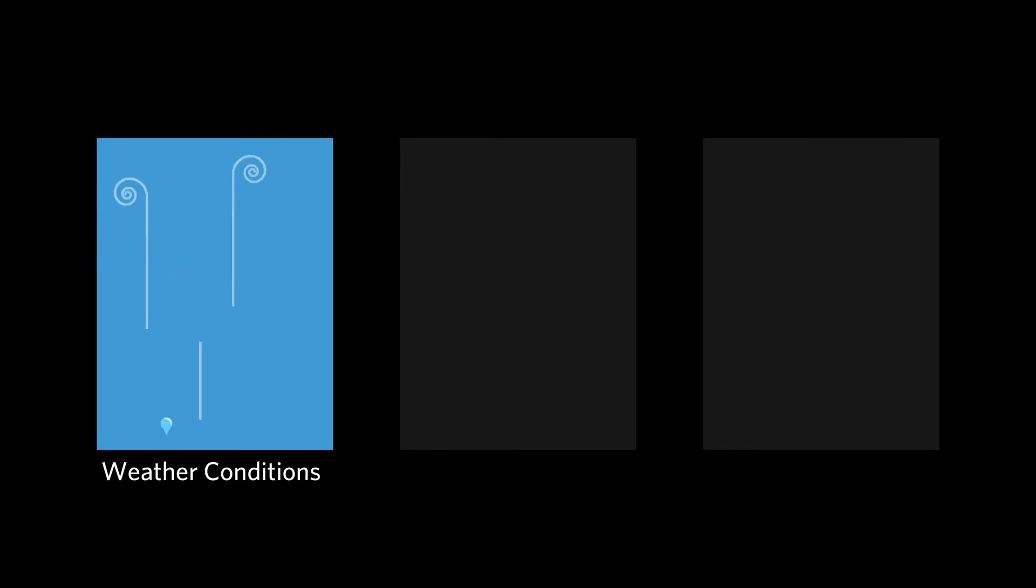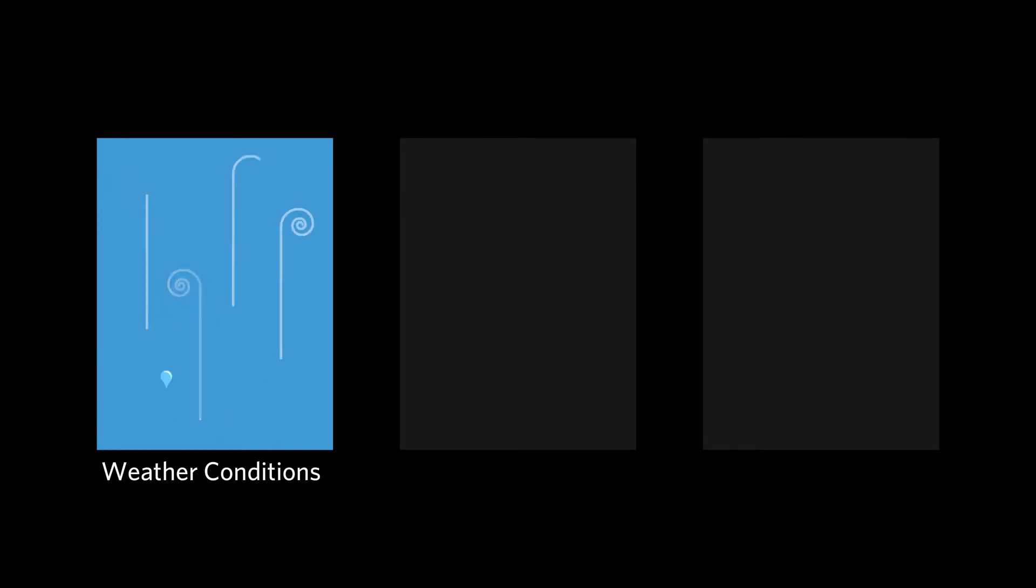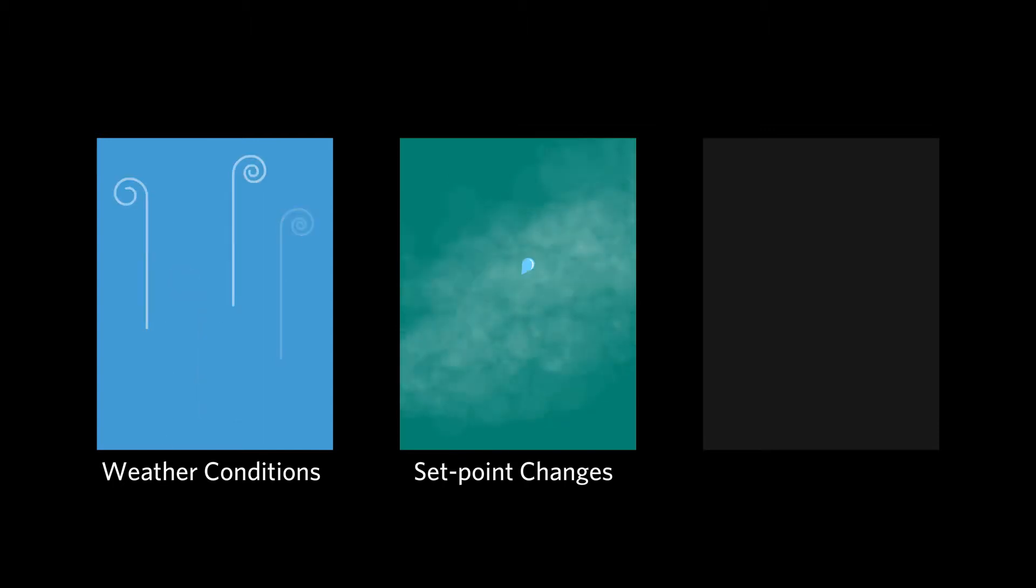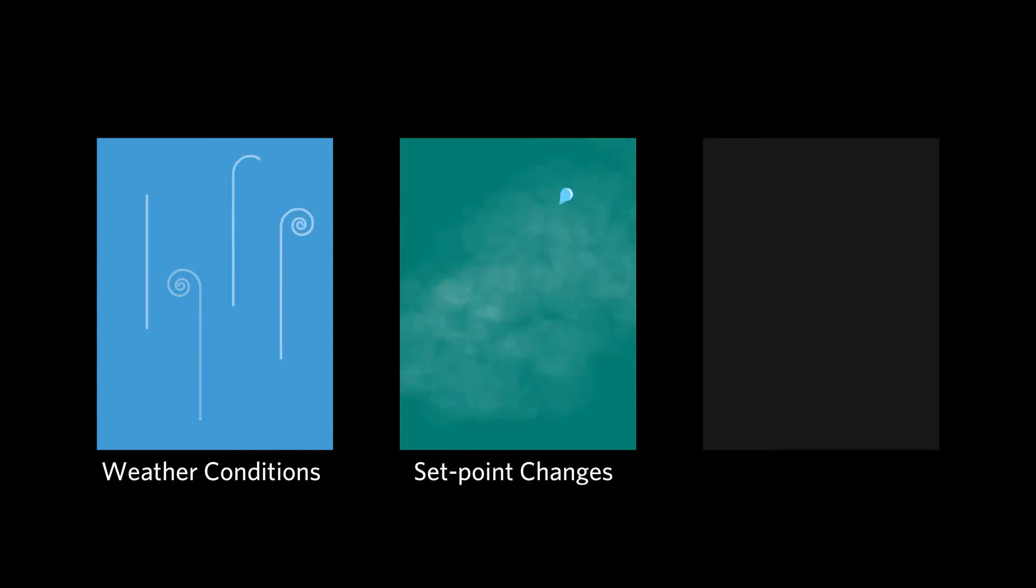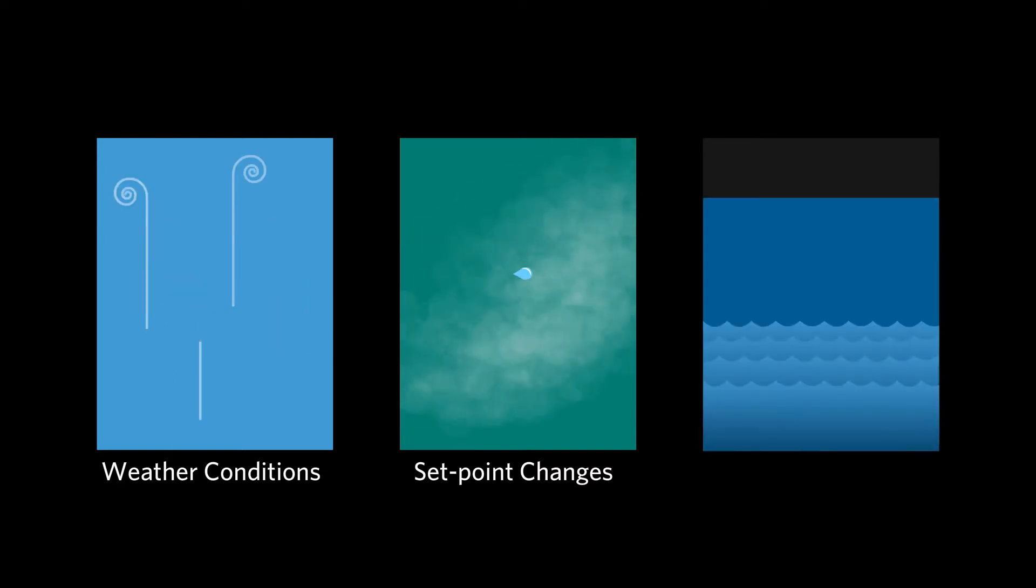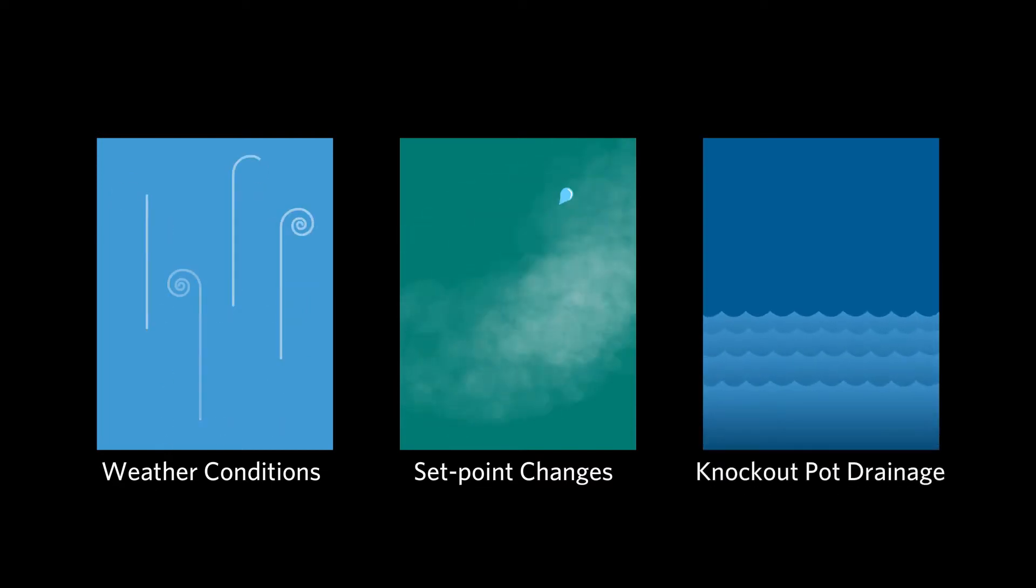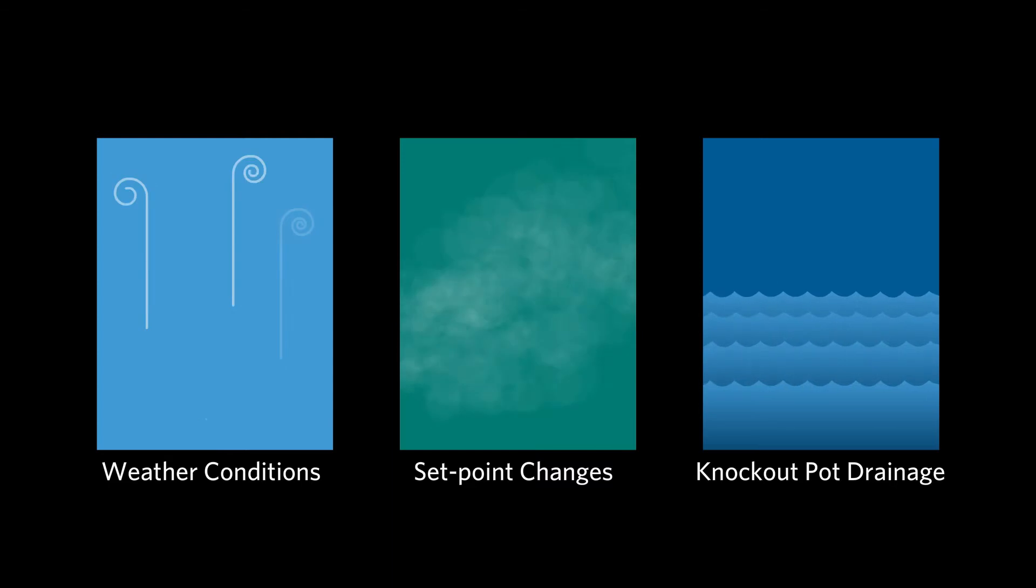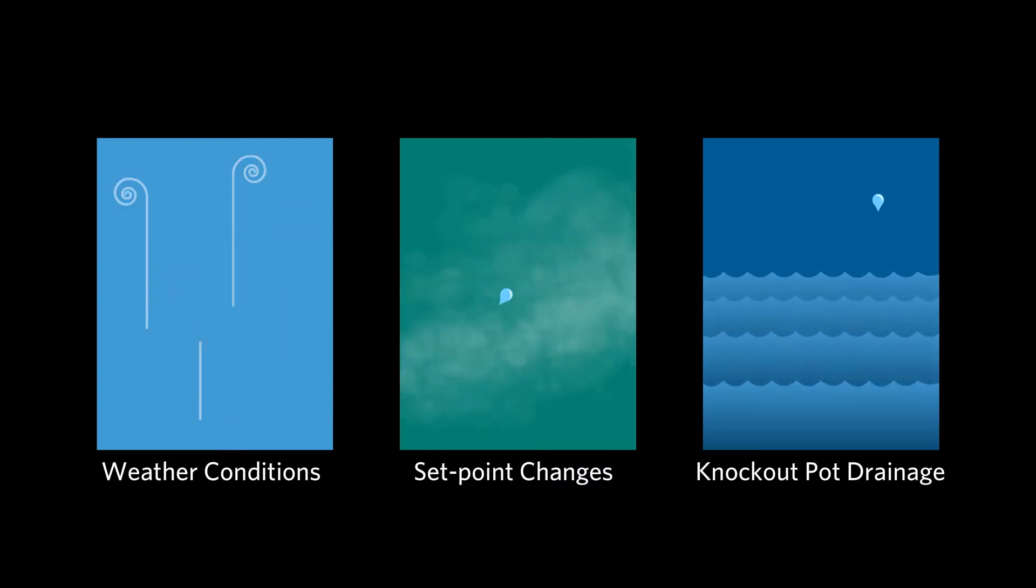Inappropriate process setpoint changes, which cause the gas to fall below the dew point so that liquid enters the compressor. And failure of scheduled manual draining of knockout pots, assuring high liquid level in the separator, encouraging liquid carryover.